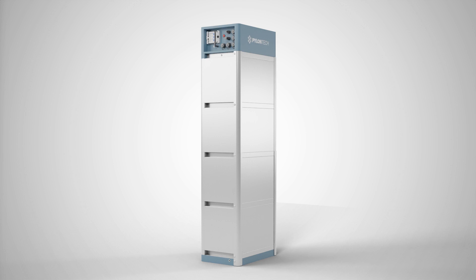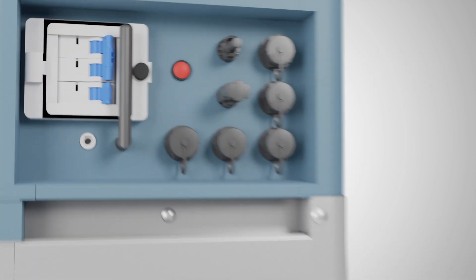The Pylontech Force H battery system is now ready for operation in conjunction with the PlentiCore. Now switch on the Pylontech battery. To do this, flip the two fuse switches and press the start button. The system has now started up and initializes automatically.